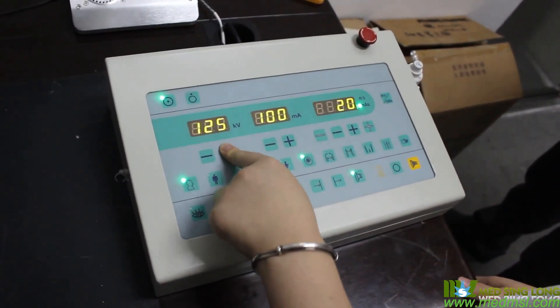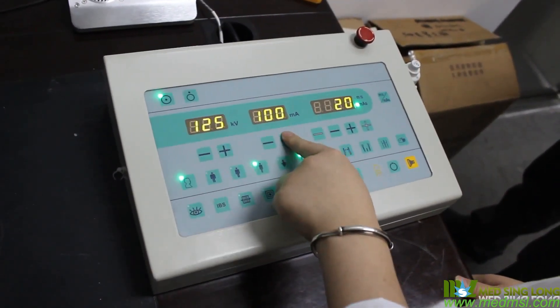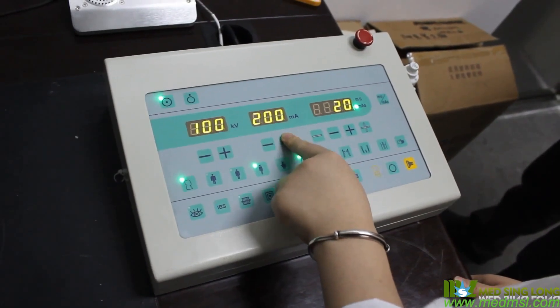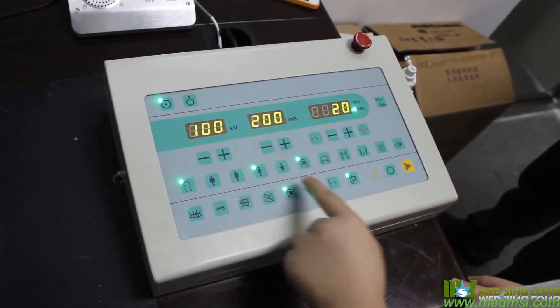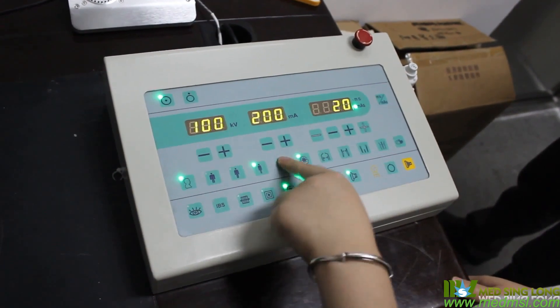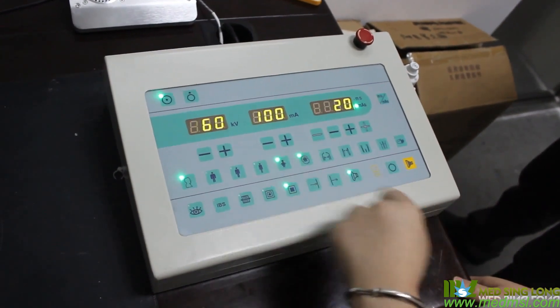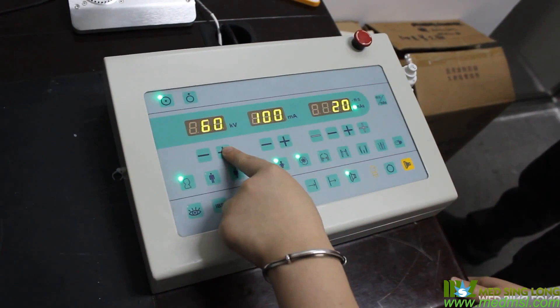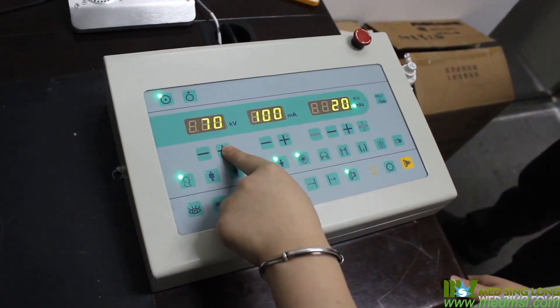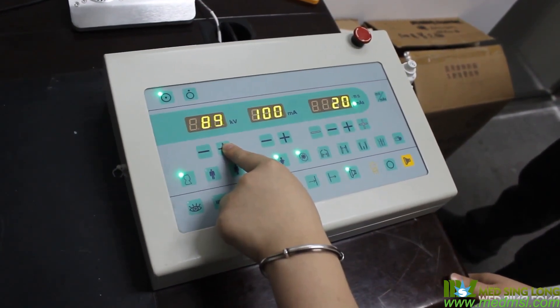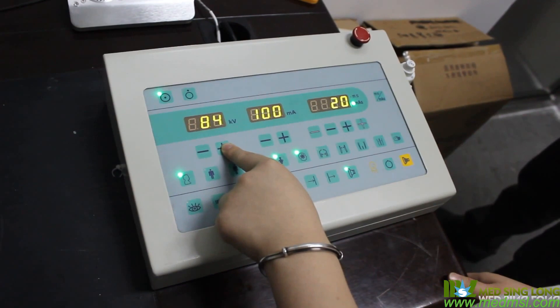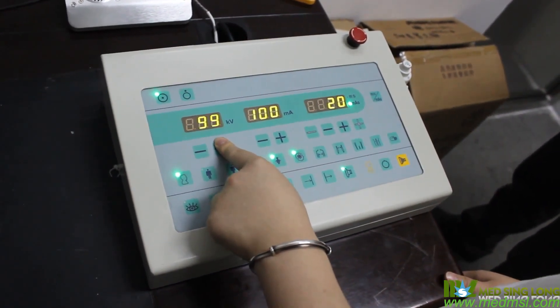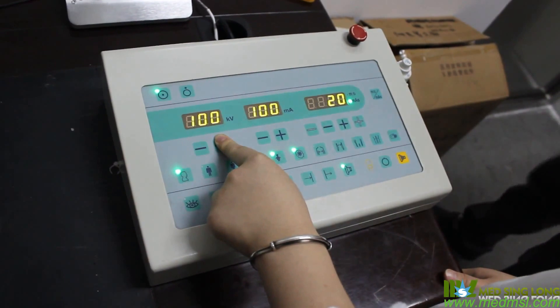In early and basic x-ray equipment, the applied voltage varies cyclically with one, two, or more pulses per mains AC power cycle. One standard way to measure pulsating DC is its peak amplitude, hence KVP. Most modern x-ray generators apply a constant potential across the x-ray tube. In such systems, the KVP and the steady-state KV are identical.